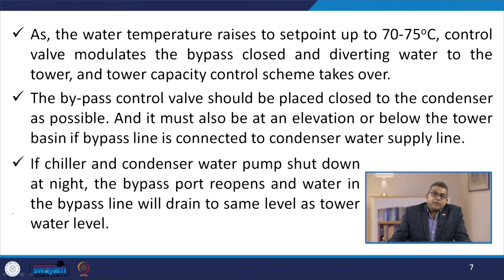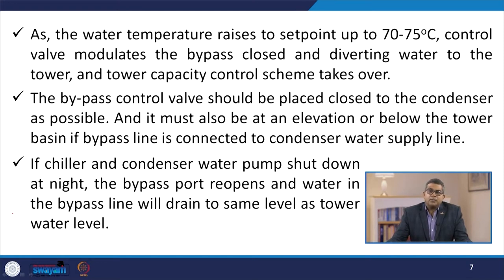As the water temperature rises to a set point of around 70 to 75 degrees Fahrenheit, the control valve modulates the bypass closed, diverting water to the tower, and the tower capacity control scheme takes over. The bypass control valve should be placed as close to the condenser as possible, and it must also be at or below the tower basin elevation if the bypass line is connected to the condenser water supply line.